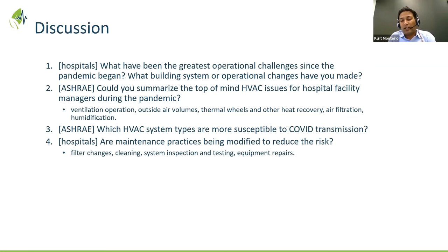A little more onerous task, but in newer hospitals—depending on the base building system—one nice thing is they tend to have airflow monitoring stations along with balancing motorized dampers, so you can make adjustments to airflows through the BAS without going up into ceiling spaces. In older constant volume systems, predominant maybe 20-25 years ago, you do have to go into the ceiling space to adjust balancing dampers, which is more challenging, and then measure differential pressure.